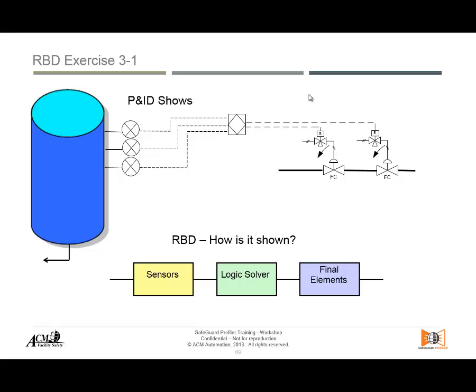The solenoid must work and the valve must work — two out of two. But if we have a complete redundant solenoid and valve beside it, then we have a one out of two of two-out-of-twos. That is the final configuration architecture of the final element. Note that this applies for a fail-closed valve; if we change to a fail-open valve, the situation changes to two out of two of one-out-of-twos.